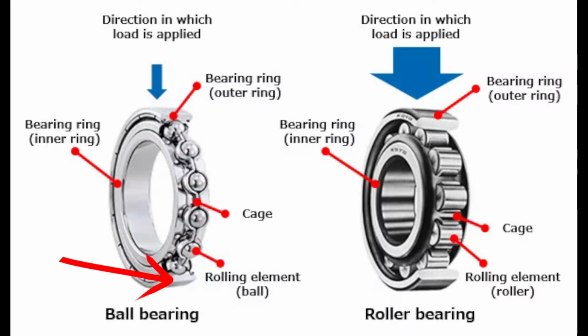And that shield on the backside helps keep that fluid grease from just getting slung everywhere, which is why if you have a set of bearings with busted shields, then the interior of the motor is going to be just coated in heavy grease residue, which will eventually lead to a premature failure due to that heavy grease. It's going to start stacking heat because the air moving through the stator can't reject the heat properly, so the stator is going to run hotter. It's going to break down the insulation faster. Then the grease is going to allow some conductance through it into making the stator short out sooner than later, or even possibly short to ground where it may have just done an internal short, right? So lots of bad things can happen when we've got busted shields.